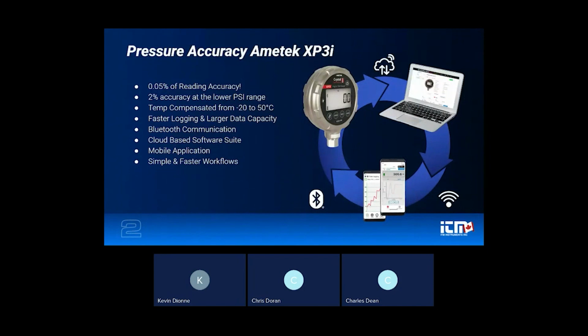So a little bit more on the XP3i. That was the instrument that you saw on the last slide. A few specifications. It offers 0.05% of reading accuracy. It's also offered in full scale if you want that, but percent of reading as well, which allows it to function confidently as a reference gauge in the field calibration applications that you may have. As I previously said, it's temperature compensated. It has Bluetooth communication. All of this feeds into simpler and faster workflow, reducing time on site while improving your consistency and documentation.